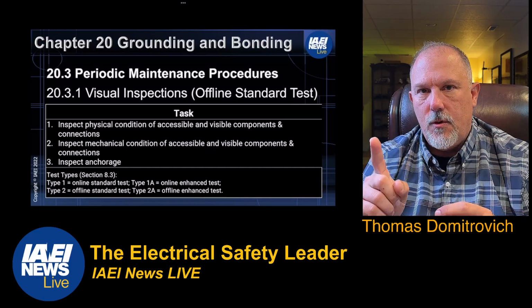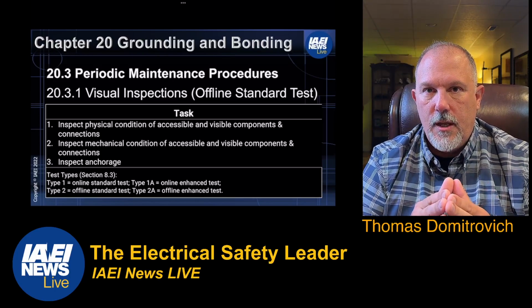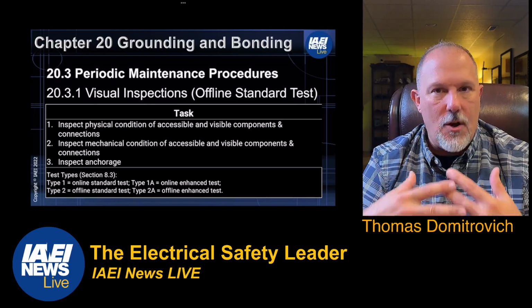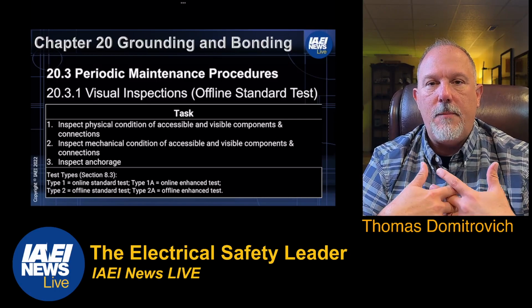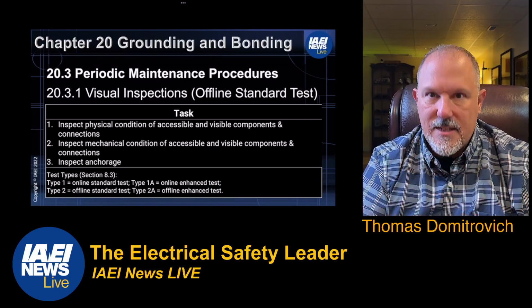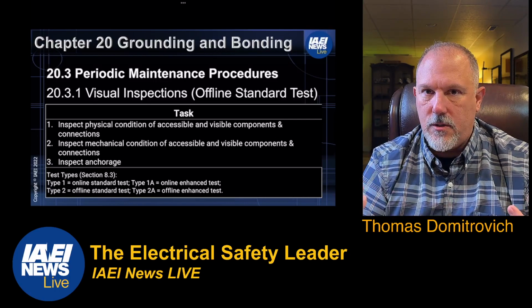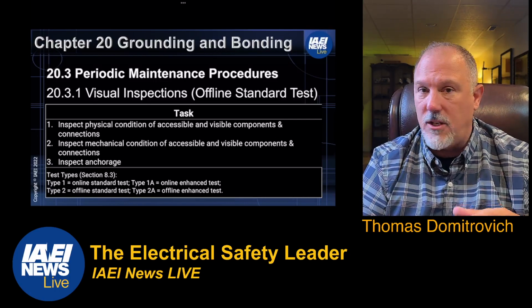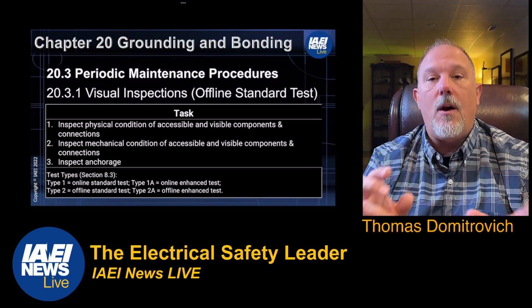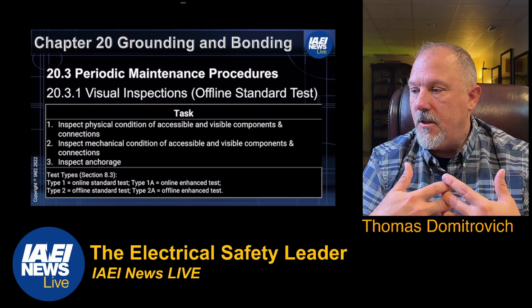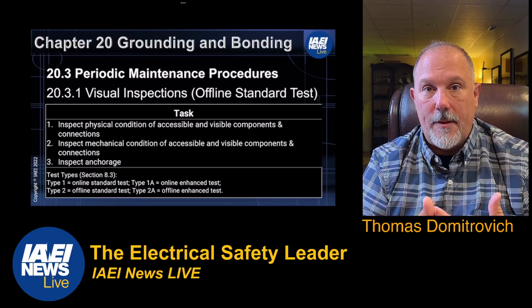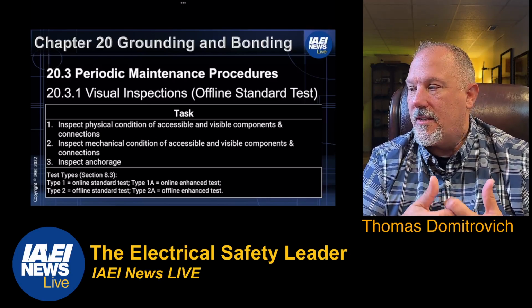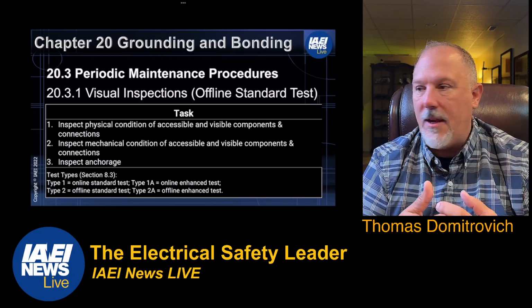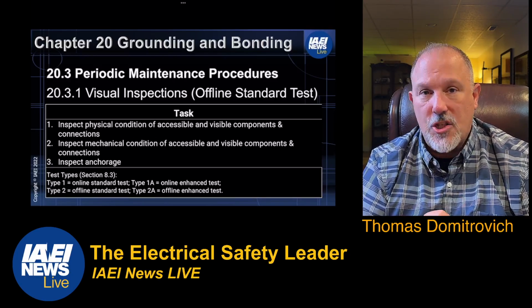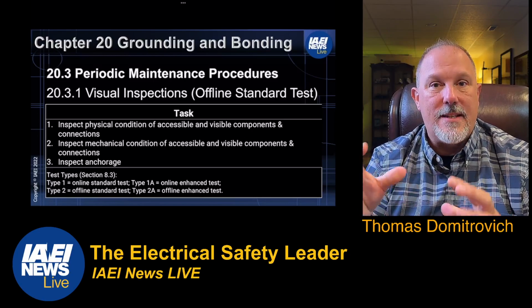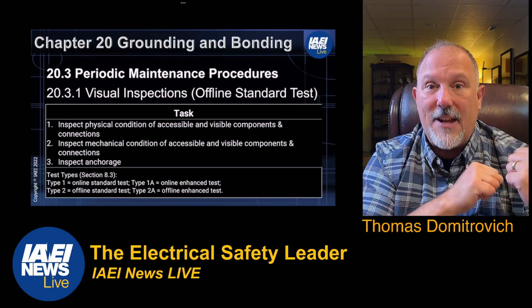What you don't want to do is, if you have a ground or whatever that's not accessible and not visible, that means you would probably need to disconnect a lot of pieces and parts just to see and do this inspection - you don't want to do that. You do not want to start disassembling the equipment just to get to a termination that may not be visible. You just don't want to do that. There are other ways to test those components, and that's going to be done in the electrical testing.